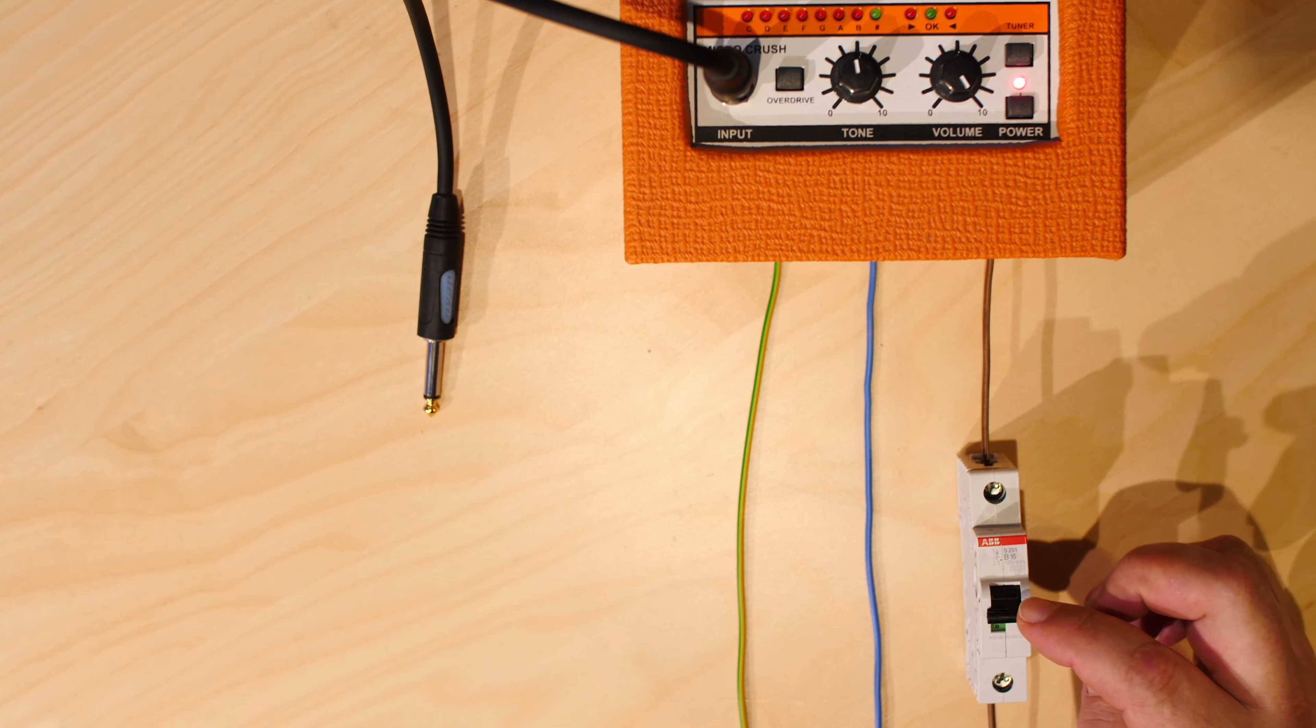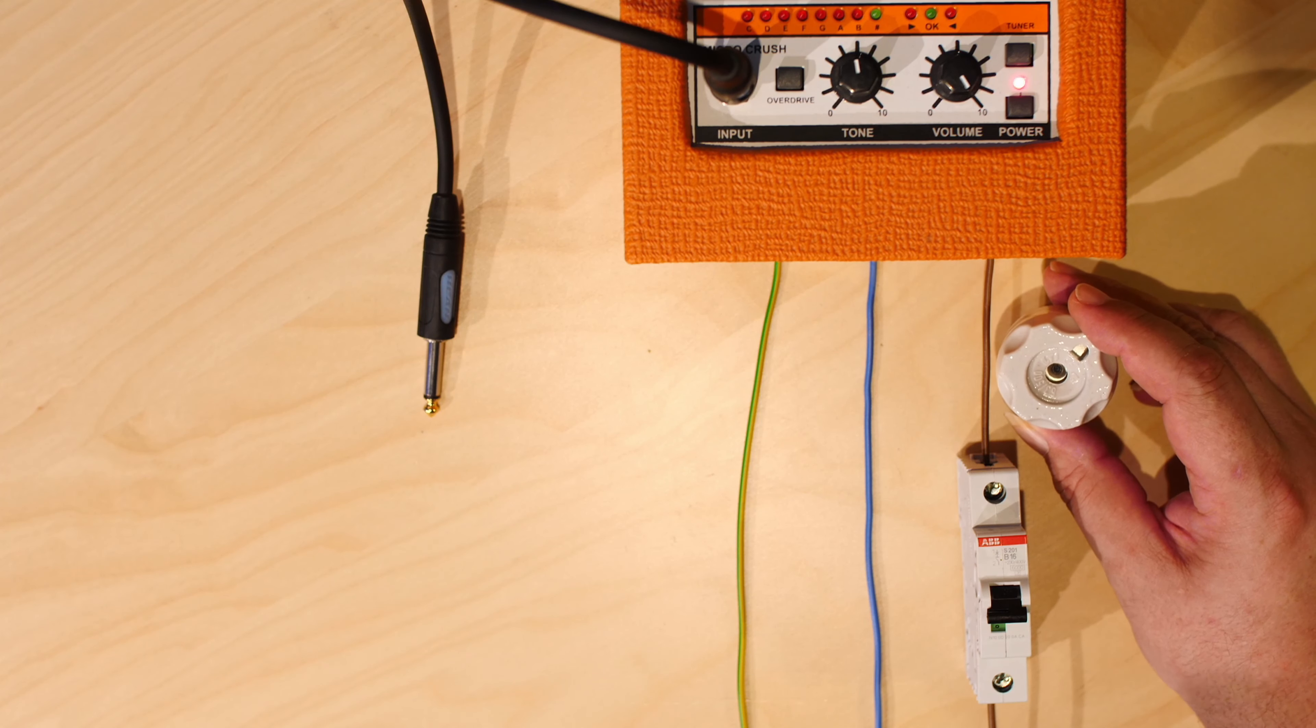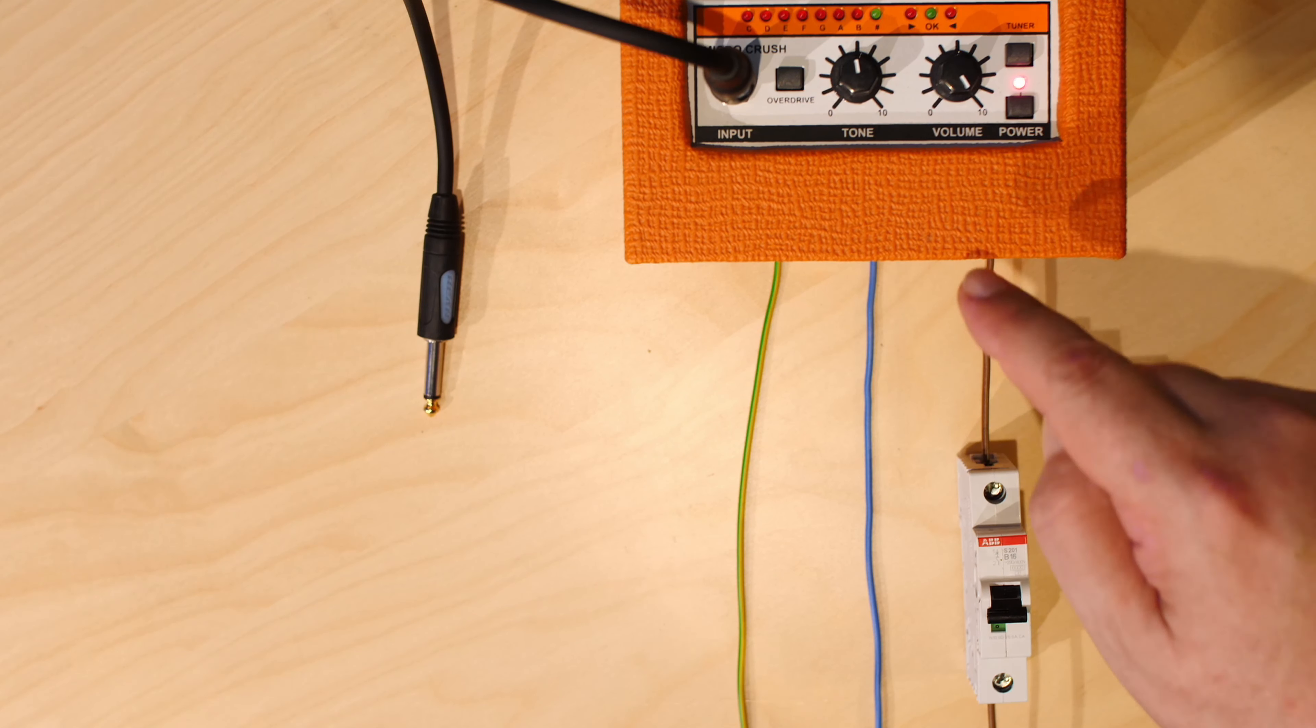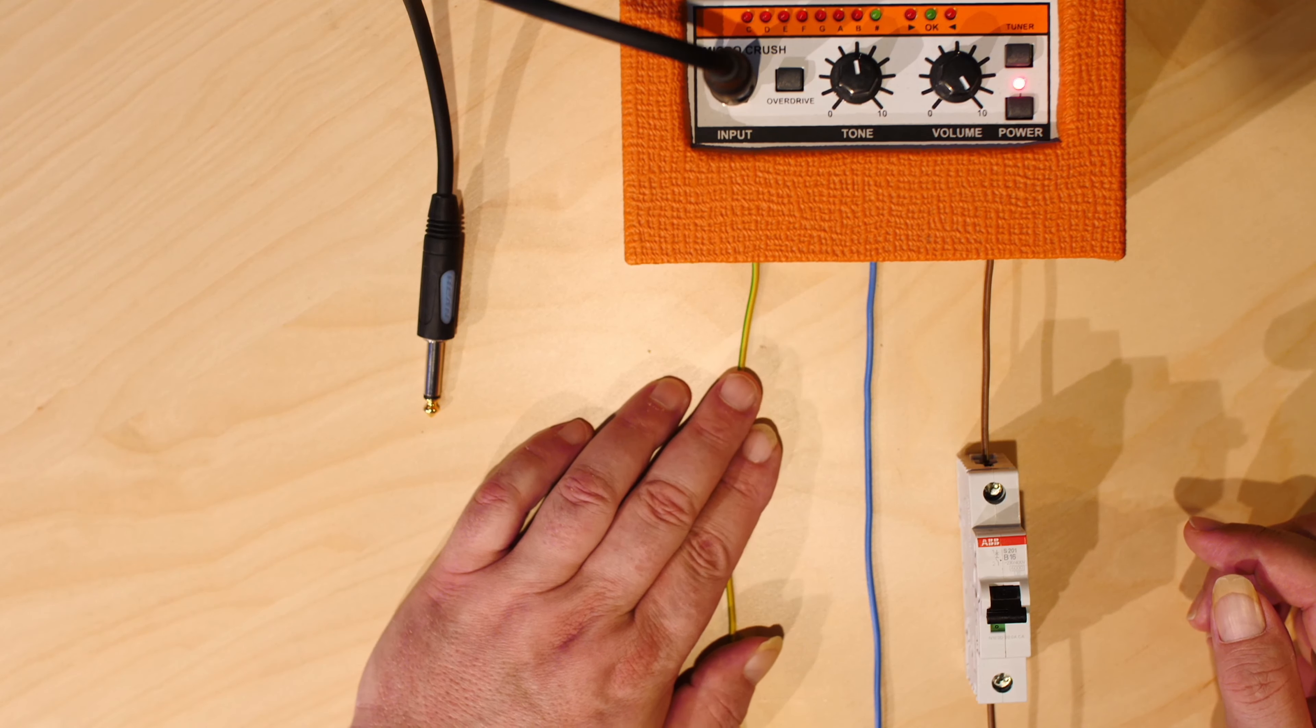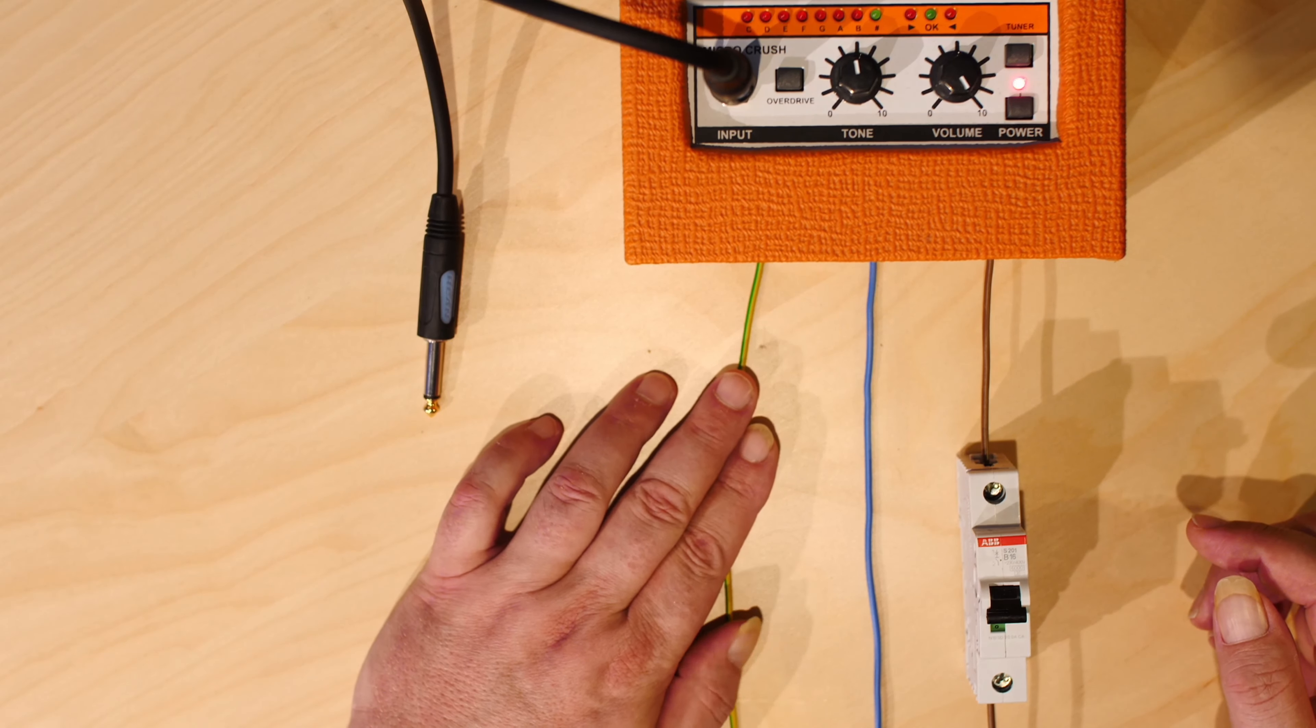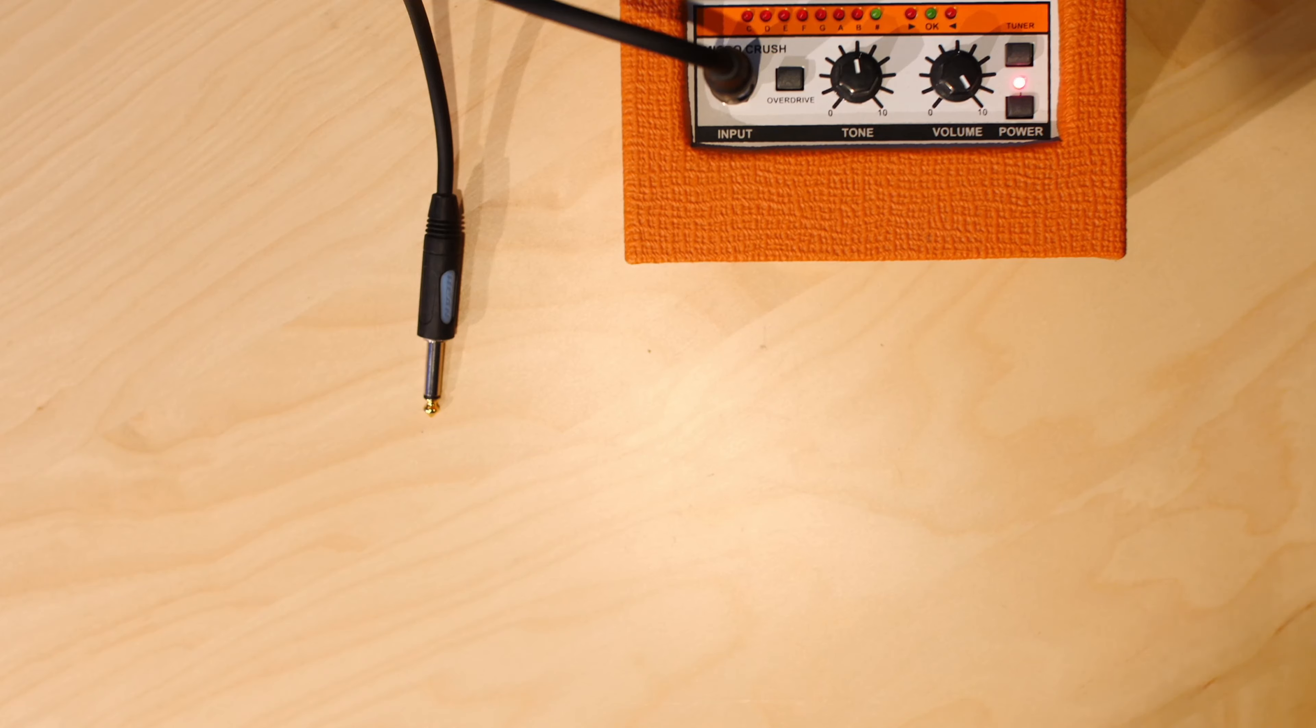Sadly, this circuit breaker, or these kind of circuit breakers, and even less, this fuse, won't react fast. It will take a few seconds. If you have bad luck, it will take a few seconds to switch off, or maybe it's just a voltage leakage, so it's not like full power going there, it's just enough to kill you, but not enough to release this. So, this is some level of protection, if you have all your equipment basically grounded properly, to ground earth, with this protective earth, the third wire, very important. And even if you don't have it, there is a solution, and that is called RCD, and I will show you now.